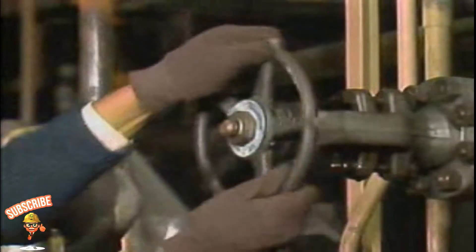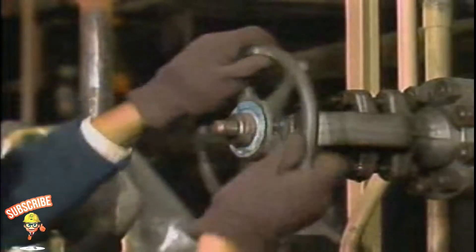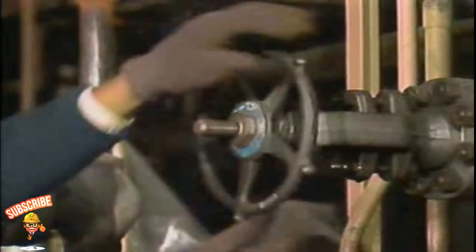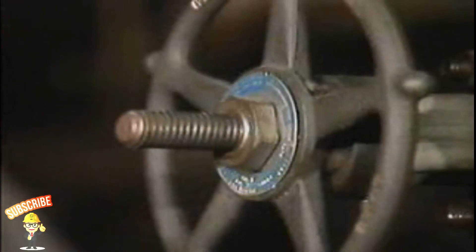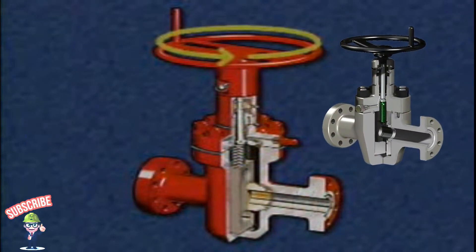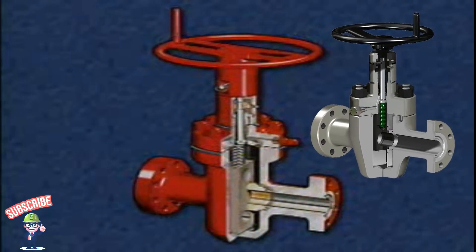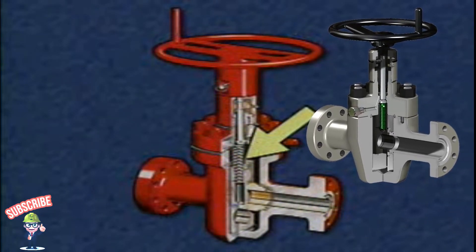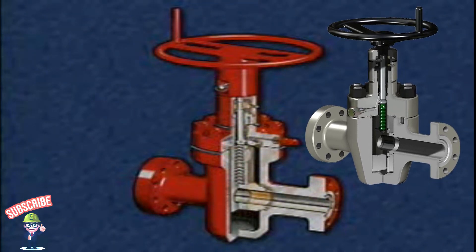Many gate valves have what is called a rising stem. In most cases, the stem rises as the handwheel is turned counterclockwise and lowers when the handwheel is turned clockwise. The amount of stem protruding from the handwheel indicates the position of the disc — if the stem is all the way down, the valve is closed; if the stem is all the way up, the valve is open. On a gate valve with a non-rising stem, the stem and handwheel rotate together. The disc is threaded to the lower portion of the stem and moves up or down the stem as the handwheel is rotated, but the stem does not move up or down.